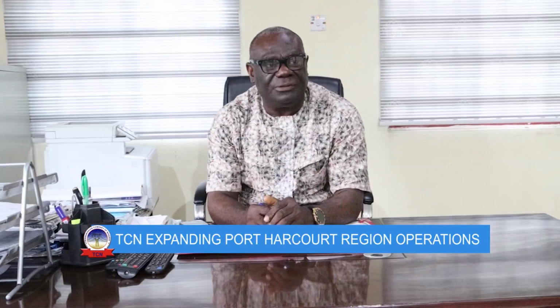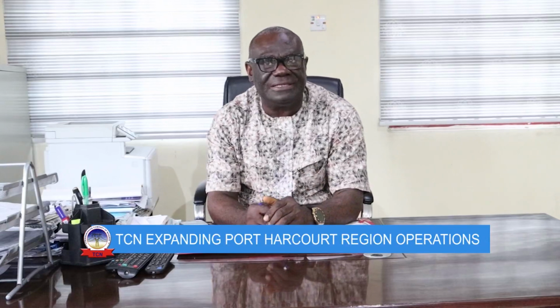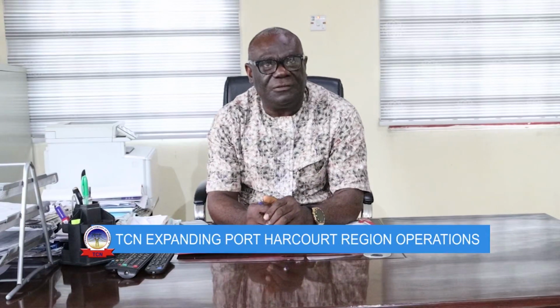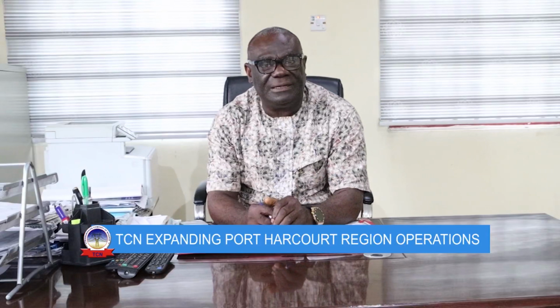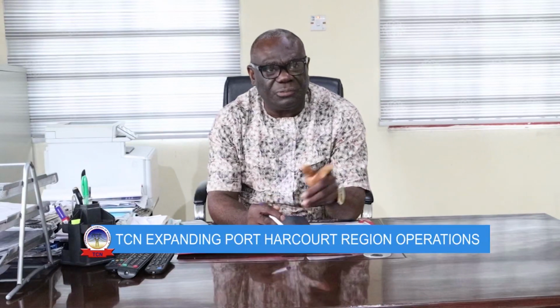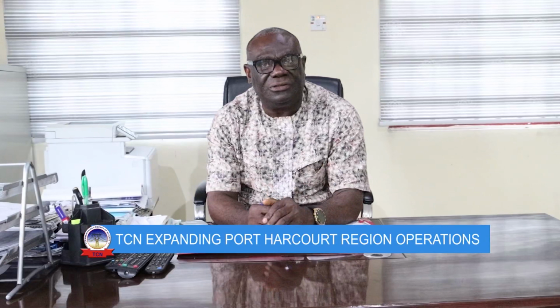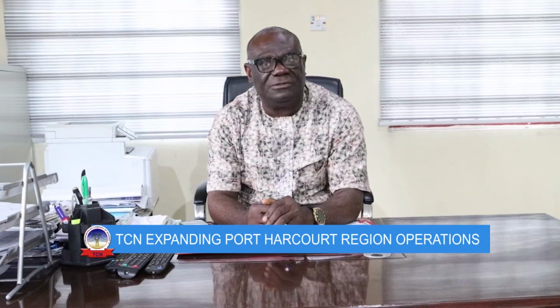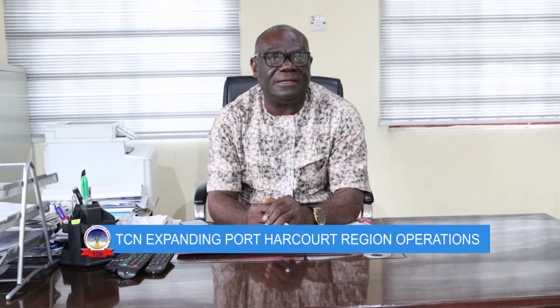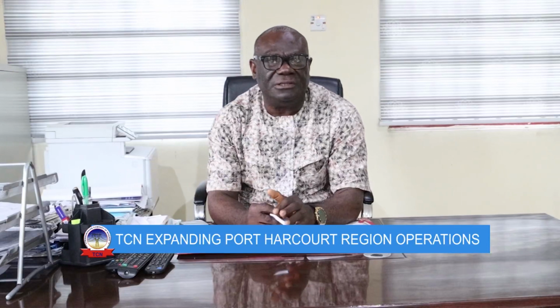Here in Port Harcourt, for instance, we have a 100 MVA transformer already on plate, and that project will come with switchyard expansion, which is in progress, along with additional feeders for dispatch — about 4 number 33 kV feeders are in that project. We have this type of project in many places.